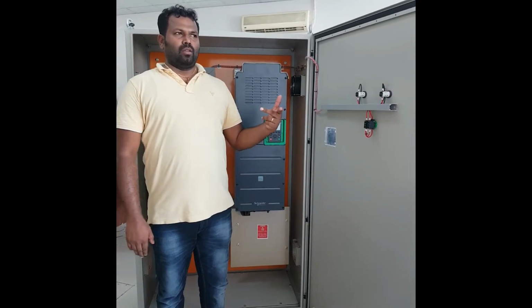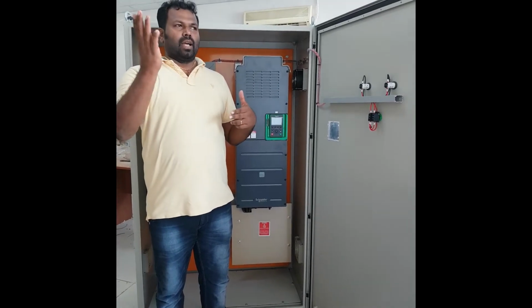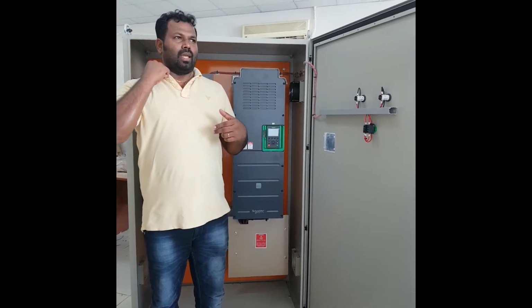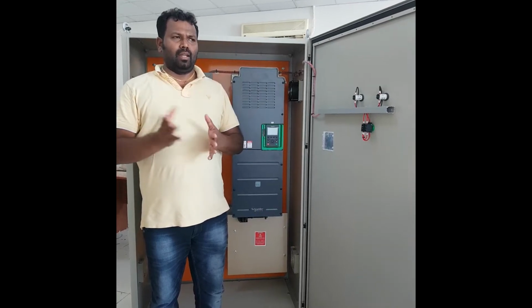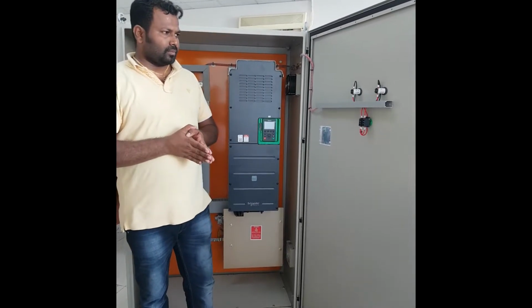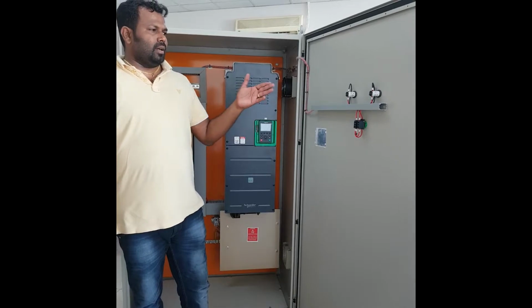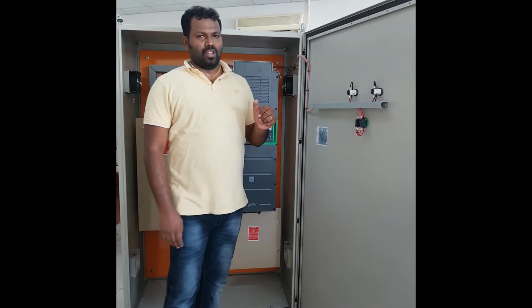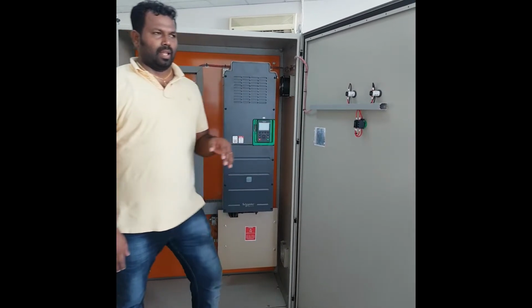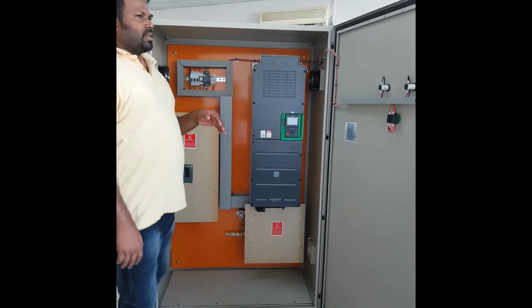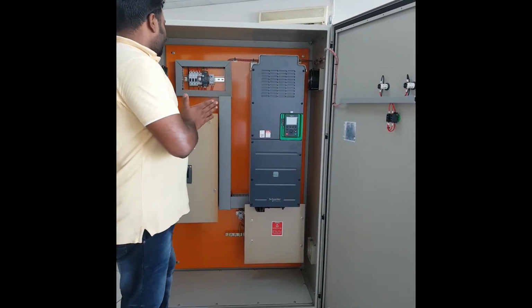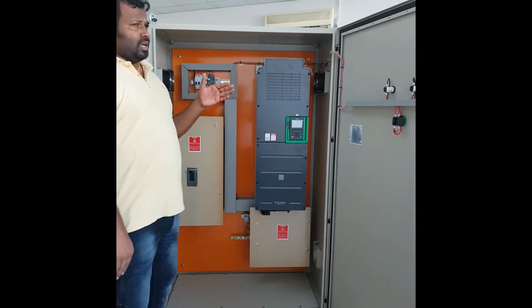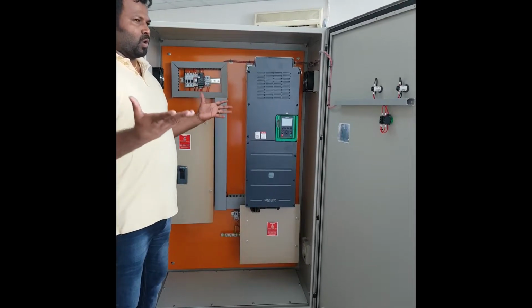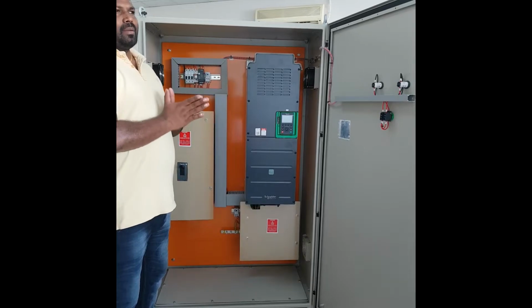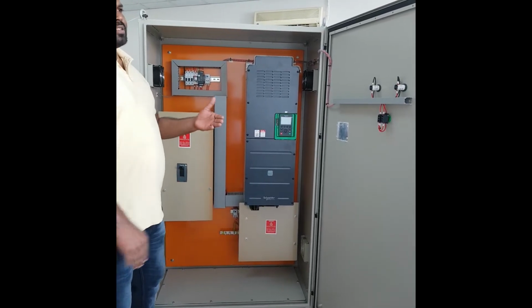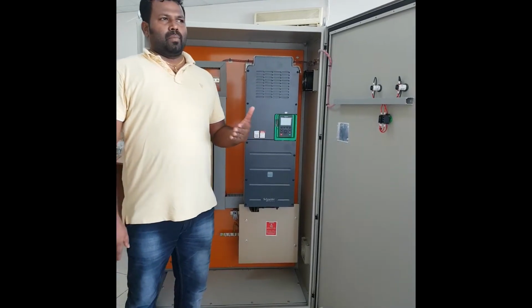With that terminal you can connect any remote start/stop command, like PLC or BMS or any external float switch. Whenever the VFD is running, we will get the run indication. Whenever the VFD trips, you will get the trip indication. The basic protection we have considered in operation is the default protection for all borewells, called dry run protection. When there is no water in the borewell, the pump should not run.